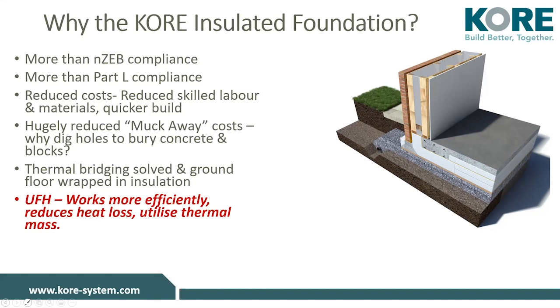For thermal bridging, we're going to wrap the whole underside of the ground floor and return that material up at the perimeter, reducing thermal bridging. If we're using underfloor heating, it's going to work more efficiently, we'll have reduced heat loss, and we'll utilize that thermal mass. We're not going to use an additional screed layer—we're putting the underfloor heating straight into the concrete slab and making that work for us.